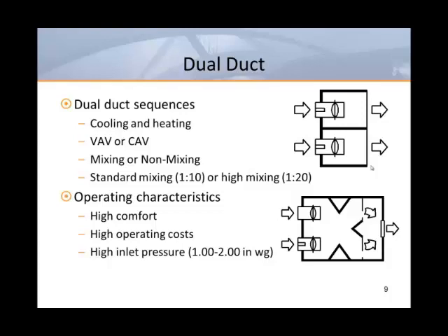There is, however, renewed interest in dual duct boxes for mixing conditioned air with air from dedicated outdoor air systems. In an application like this, an optional water coil at the discharge of the unit could be used for heating without the need to actually reheat.